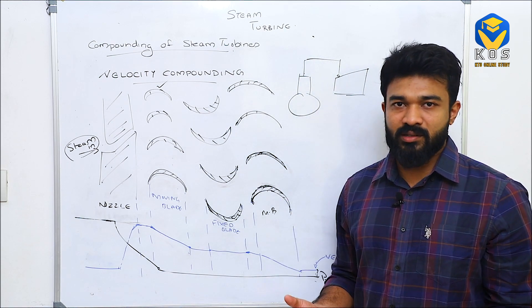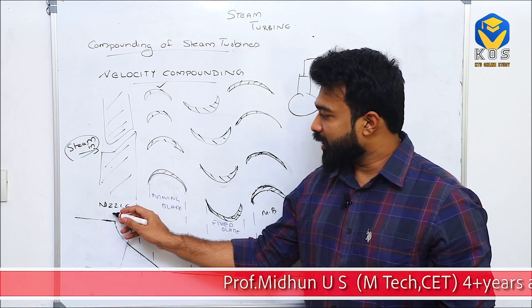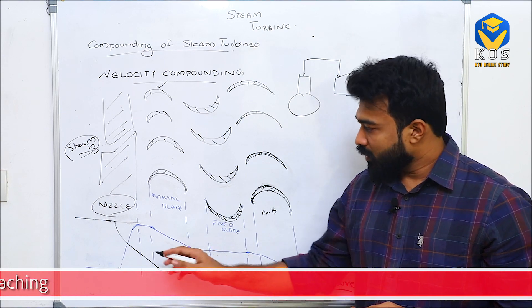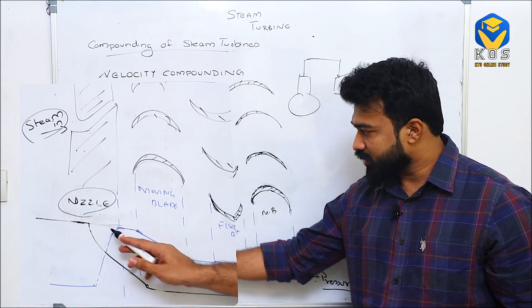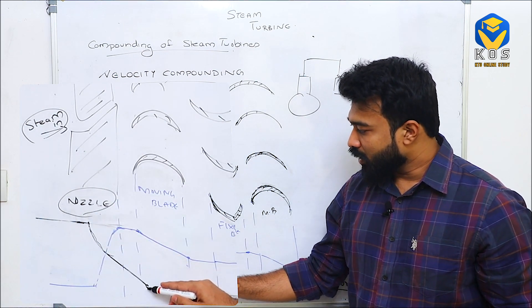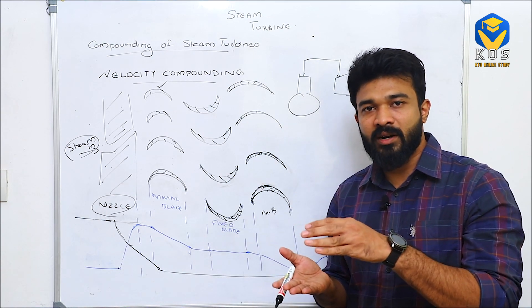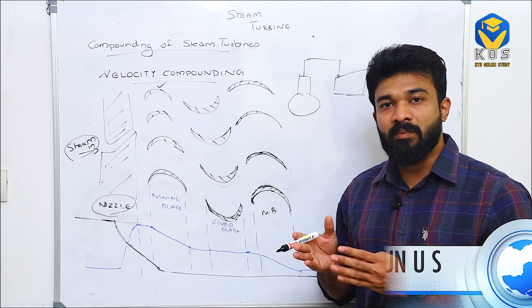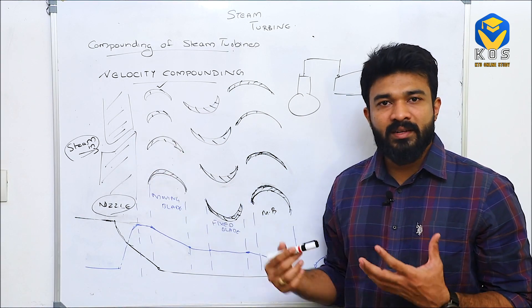This high pressure is not directly useful for us in the turbine. We need to convert this high pressure. We use a nozzle as a device. The nozzle has no moving parts — it uses area variation. The blue line is the velocity and the black line represents pressure. High-pressure steam passes through and moves to a very low pressure, so velocity increases from low to very high. Now we have low-pressure, high-velocity steam at the nozzle outlet.